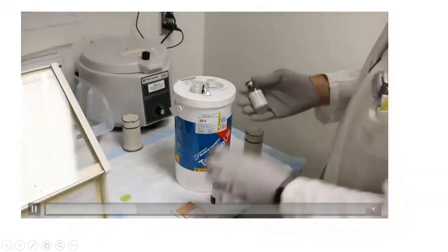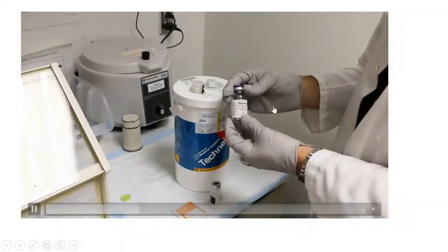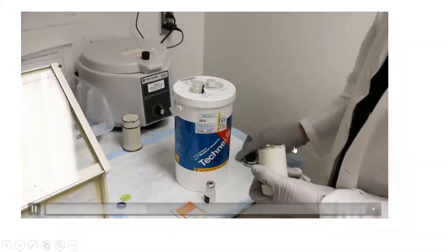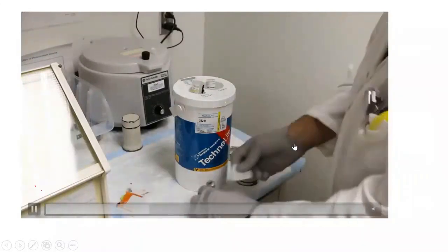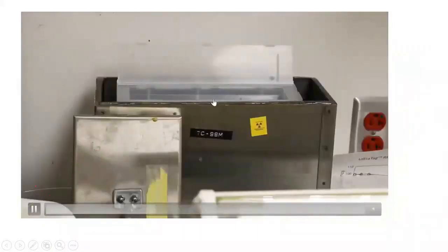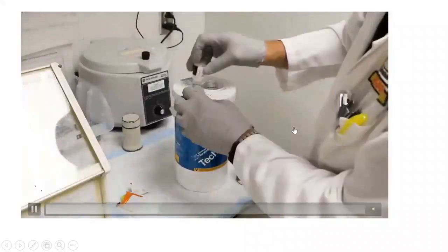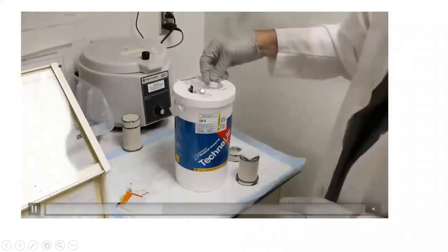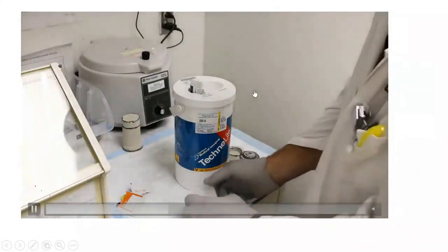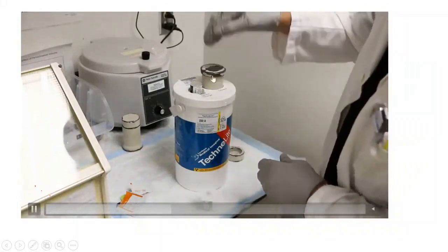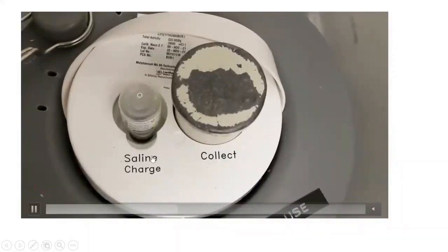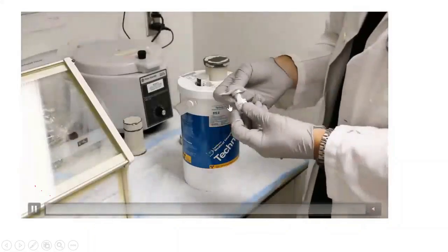What is he doing? He will start by placing the evacuated vial in the lead shield to avoid exposure to radiation. He opens the lead shield, puts the vial inside, closes it, and sterilizes it with a swab. He removes the old vial and throws it in the waste. Then he puts the saline first and then after that. This removes the evacuated vial, and I place it in the shield so that it does not expose itself for the elution process. Now the elution process begins, and the line comes down and starts to gather.